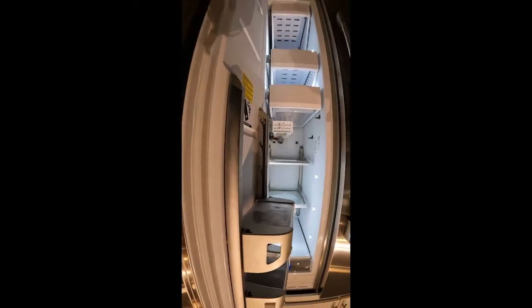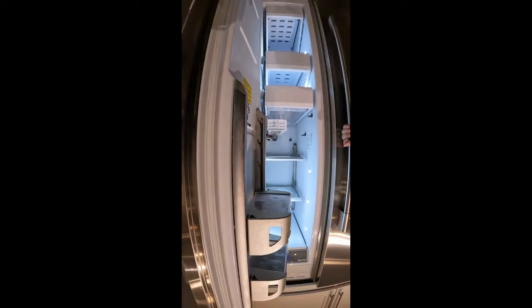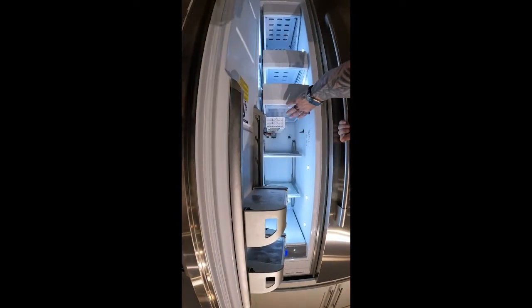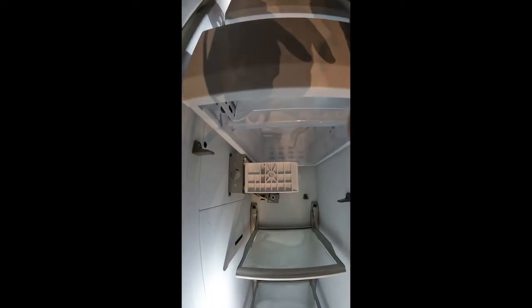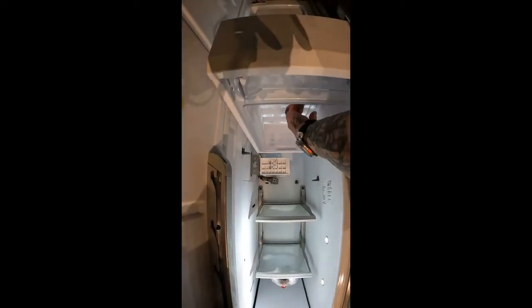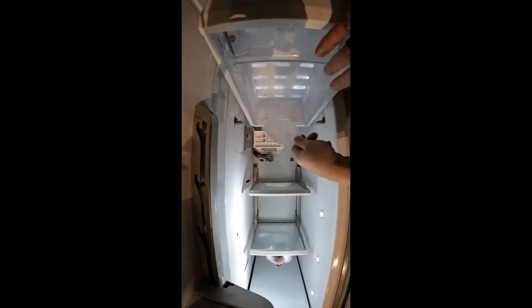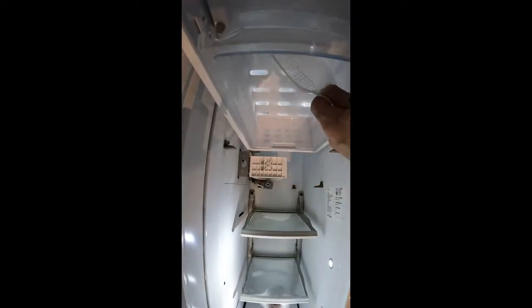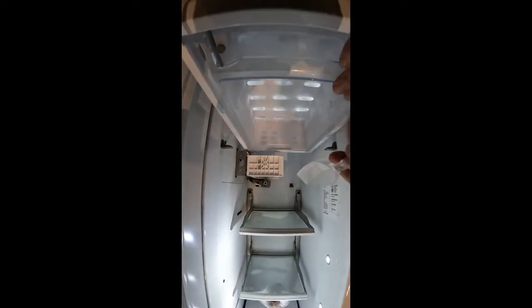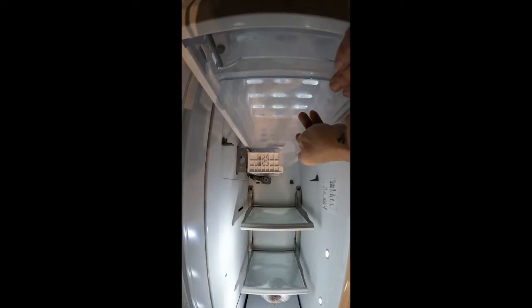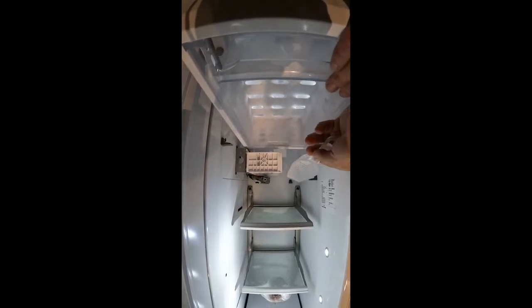Customer might have some issues where the ice is clumping together and things like that, which kind of brings me to my next point. So if you look at where the ice maker is located in this ice bucket, when the ice drops, it's going to drop towards the back of this ice bucket. Every time it dumps ice and harvests, it's going to fall into a little mountain in the back corner of that ice bucket. When the customer goes to get ice out of here, what we recommend is using your ice shovel and raking that ice forward, so that way it's a nice flat level. The bail arm has room to drop down, does not notice that mountain of ice in the back, and then does not drop ice anymore.